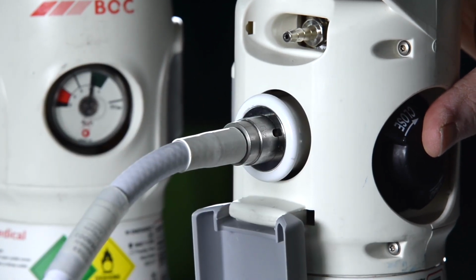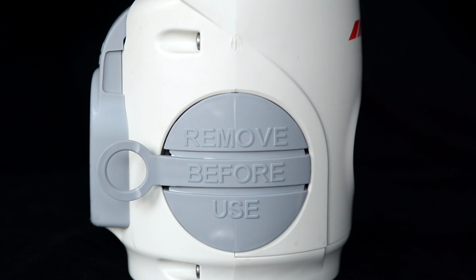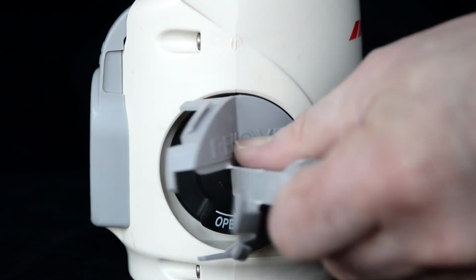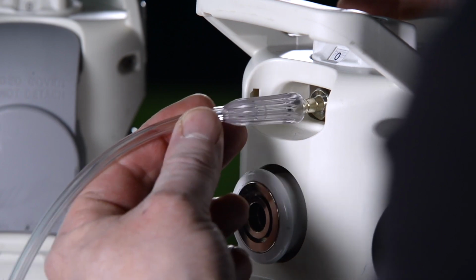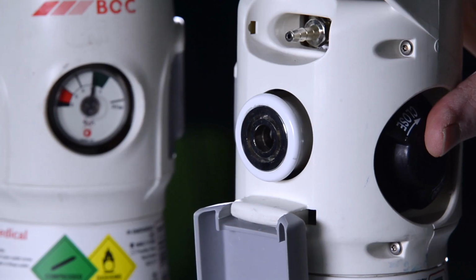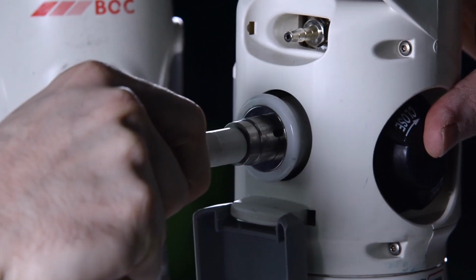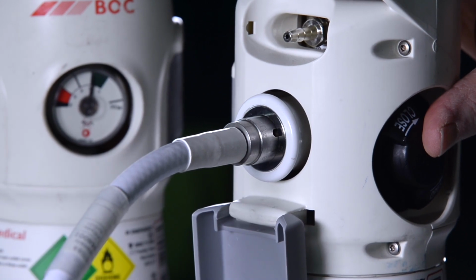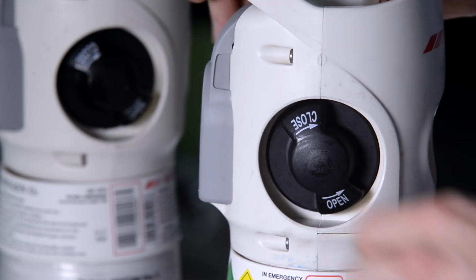Remove the seal fitted over the valve hand wheel by pulling the tab. Discard this seal once removed. To connect tubing to the fir tree outlet, push the tubing firmly into place. To connect a probe to the Schrader outlet, push the probe into the Schrader and it should click as it engages. Open the cylinder valve slowly.